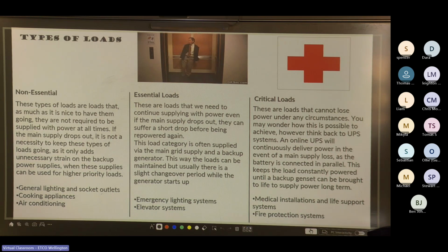Critical loads. These are loads that cannot lose power under any circumstances. So yeah, the only way to achieve that is with a UPS system. So an online UPS will continue to deliver power, even in the event of a main supply loss, as it's connected in parallel. This keeps the load constantly powered until a backup genset can be brought on to supply power. So medical installations and life support systems, and your fire protection system. So normally your fire protection systems also have a battery built into them. If you open any of the fire panels that you see in commercial buildings, you'll find a small, it's not a car battery, but a small battery inside of it. It's about the size of, say, 4 drill batteries, yeah. Or a couple of the big chunky DeWalt ones. Cool. So non-essential, essential, critical.